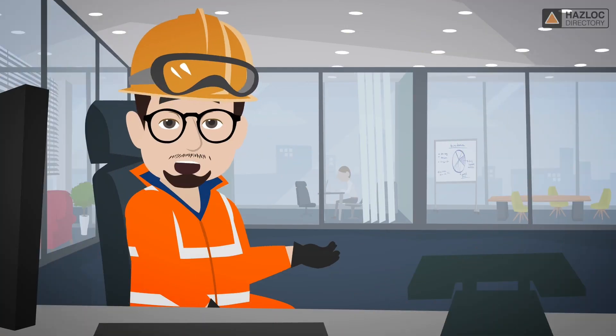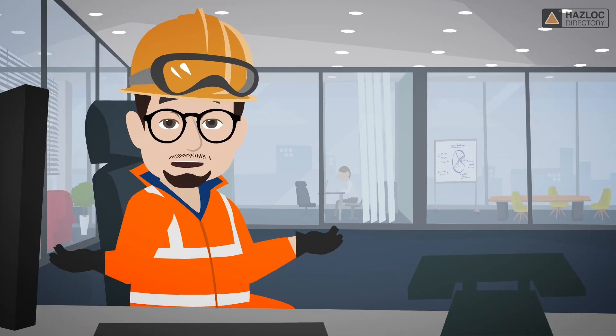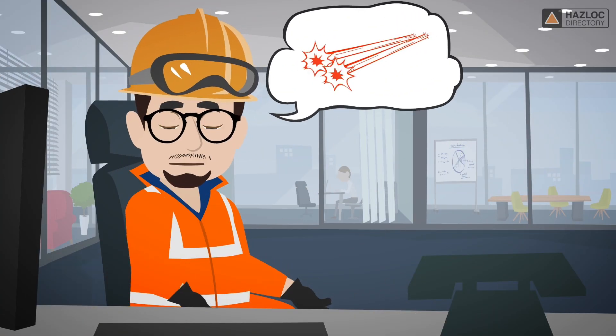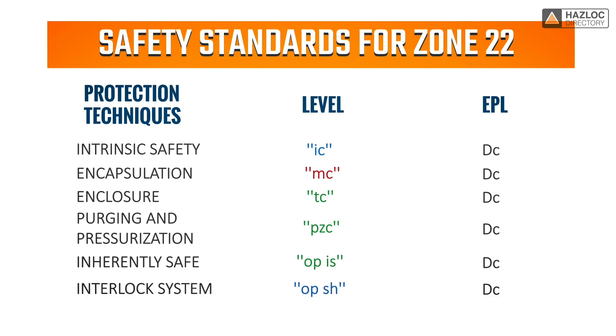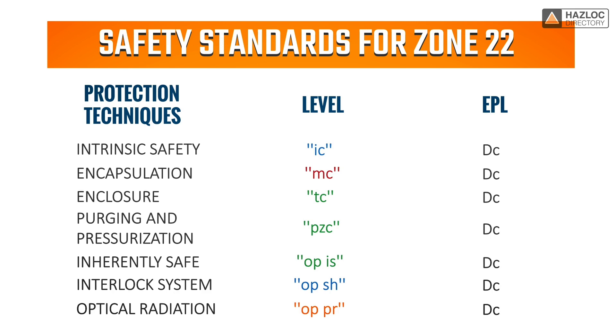Additionally, equipment with optical radiation features such as lasers can be installed in Zone 22 if the optical power is inherently safe using OP-IS protection, or an interlock system complying with OP-SH protection, or using protected optical radiation complying with OP-PR, with an equipment protection level, or EPL, of DC.